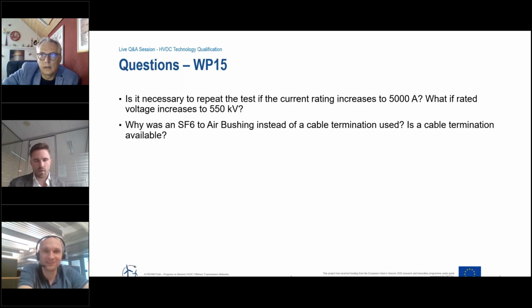I would also try to answer this question. We've designed the HVDC GIS to be able to operate with overhead lines and also with cables. So we have the SF6 to air bushings available, and we also have a cable termination available. If we purely look at the GIS, if it is specified for connection to an overhead line, we would have higher impulse overvoltages, for example, the lightning impulse overvoltage.